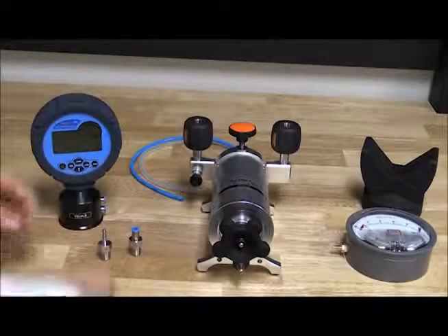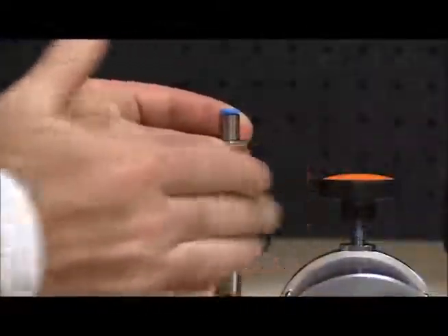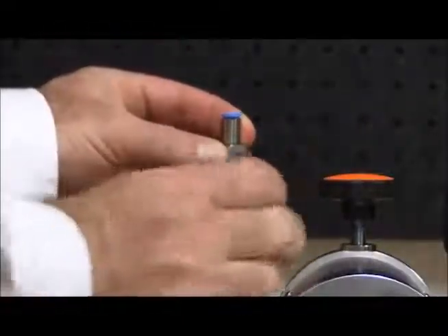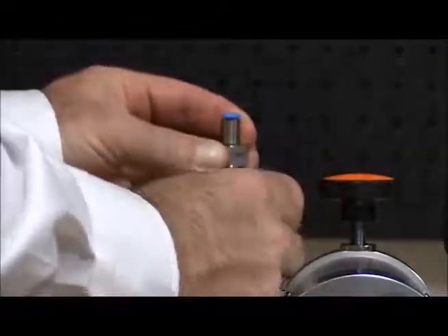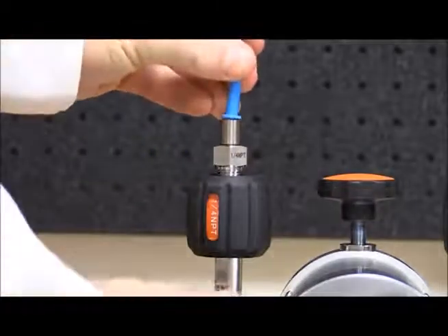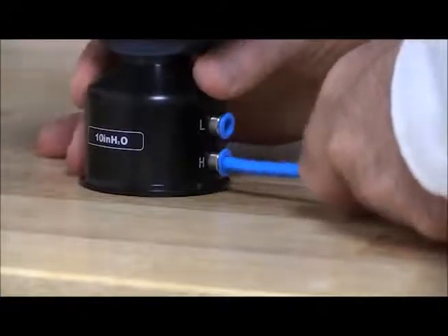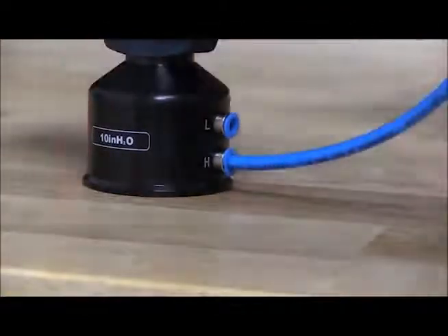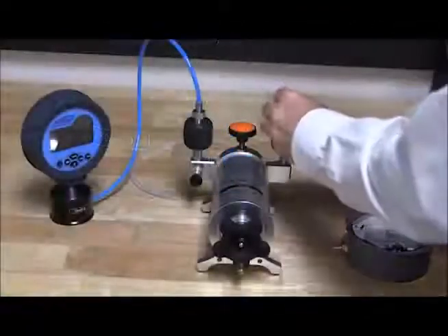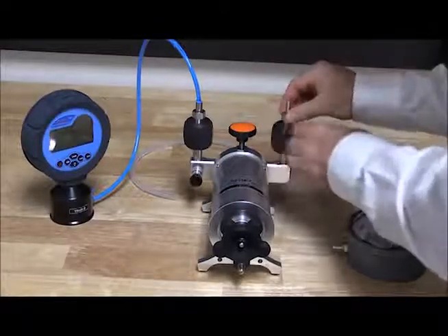For this method we will connect the high ports for both the reference and the device under test, or DUT, to the 901 pump, leaving both low ports open to atmosphere. Most Additel pumps come with easy-to-use hand-tight quick connectors that do not require PTFE tape or wrenches. The Additel 681 differential pressure gauges also connect with easy-to-use quick connectors.